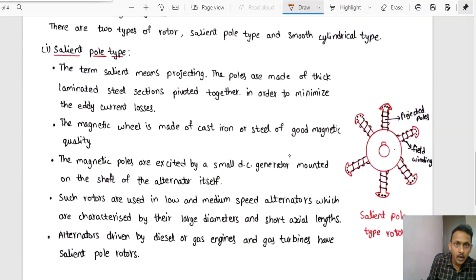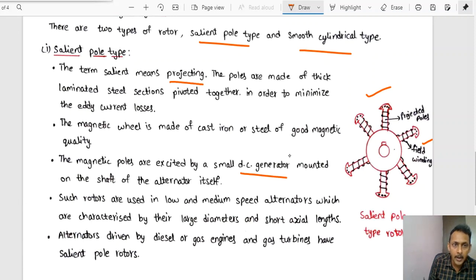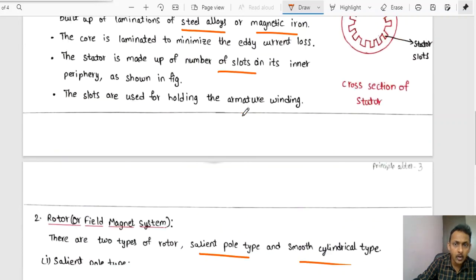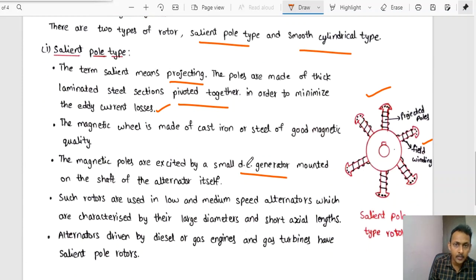With respect to the rotor or magnetic field system, there are two types: salient pole type and smooth cylindrical type. In the salient pole type rotor, projected poles carry the field winding, which is excited by a small DC generator mounted on the shaft of the alternator. The poles project outward and are made of thick laminated steel sections bolted together to minimize eddy current losses. The core is laminated to reduce eddy current losses.